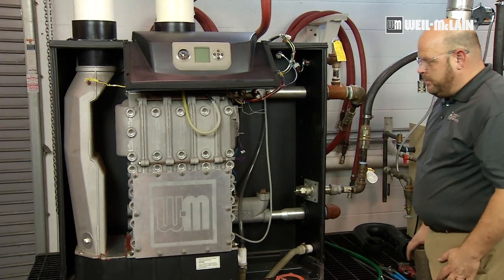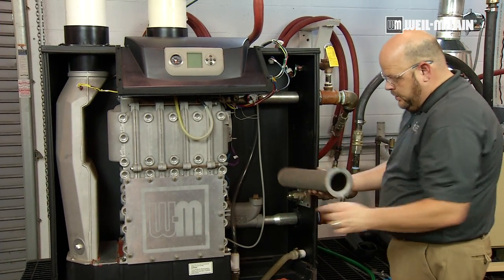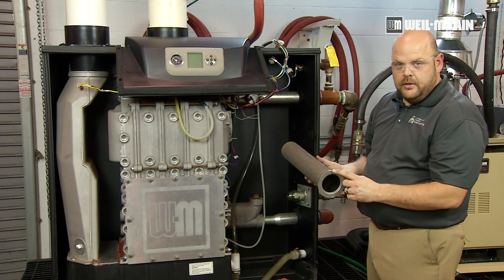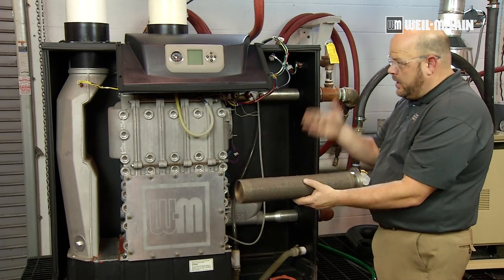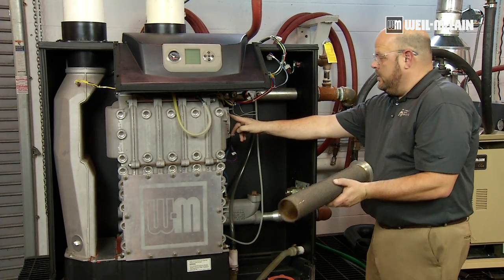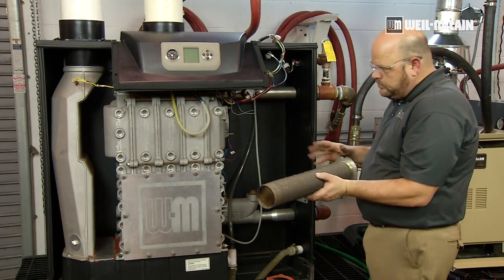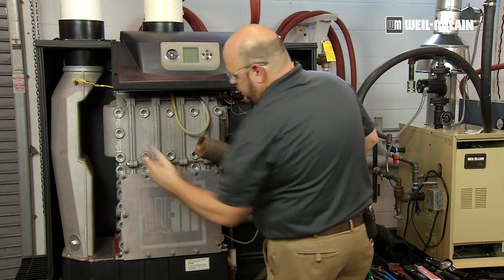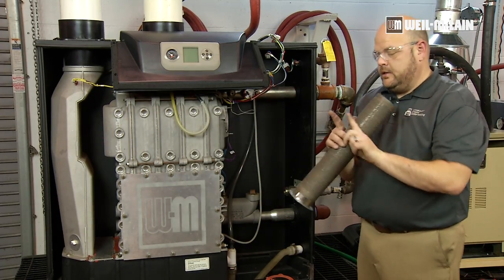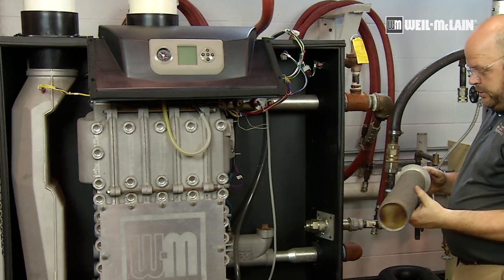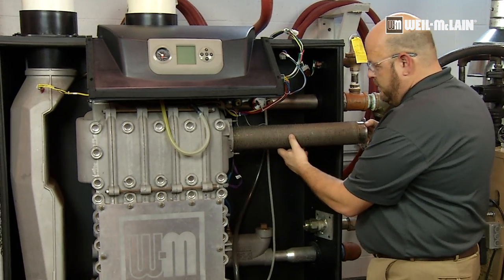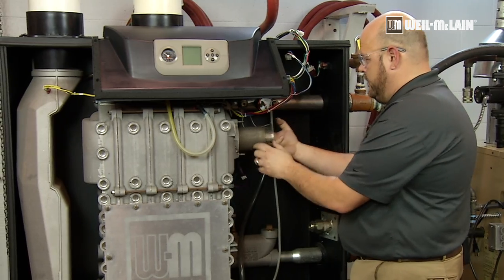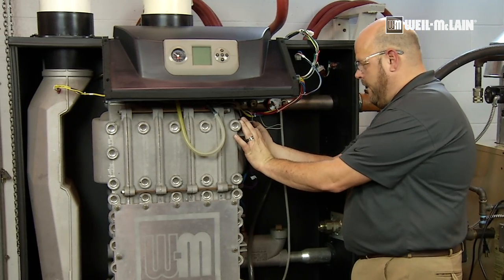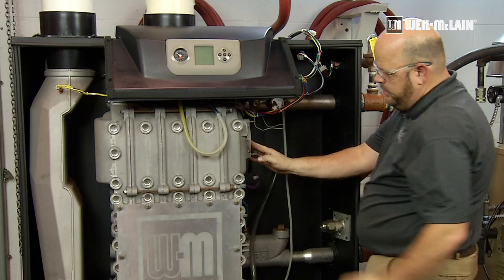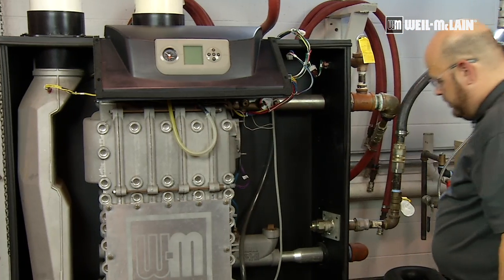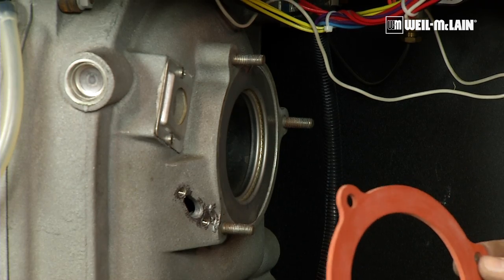And now we're going to put our burner back in. If you look at the end of the burner, there's a notch. The notch is at 12 o'clock, right at the top on the flange. In the back of the burner, there's a V notch. We'll set the burner, feed it through the front, and set it right down on the V, and then into place, and it'll be resting on both ends. And we'll install the burner gasket.